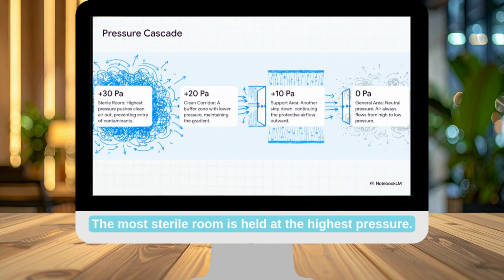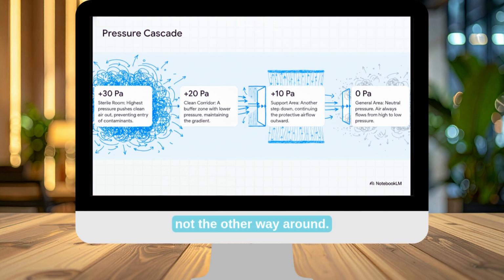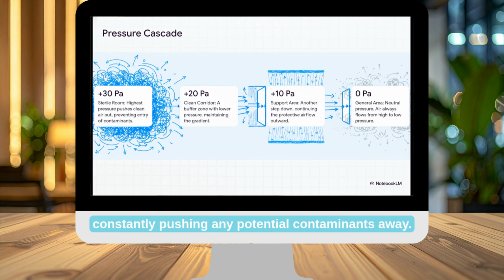The most sterile room is held at the highest pressure. The hallway right outside is at a slightly lower pressure, the support area is lower still, and the general area is neutral. Since air always flows from high pressure to low pressure, anytime a door opens, clean air flows out of the sterile room, not the other way around. This pressure cascade creates an invisible barrier, constantly pushing any potential contaminants away.